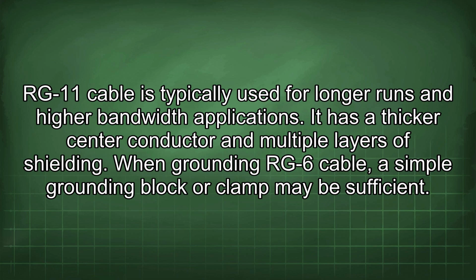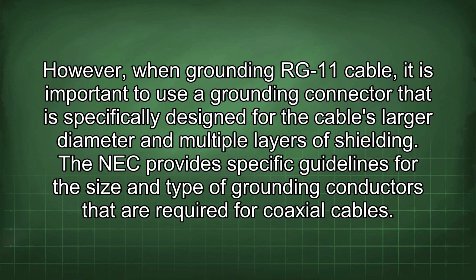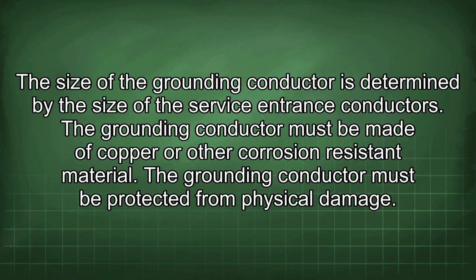When grounding RG-6 cable, a simple grounding block or clamp may be sufficient. However, when grounding RG-11 cable, it is important to use a grounding connector that is specifically designed for the cable's larger diameter and multiple layers of shielding. The NEC provides specific guidelines for the size and type of grounding conductors that are required for coaxial cables. The size of the grounding conductor is determined by the size of the service entrance conductors. The grounding conductor must be made of copper or other corrosion-resistant material. The grounding conductor must be protected from physical damage.